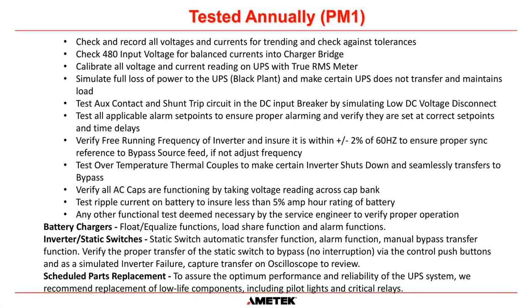We also test the over temperature thermocouples. So there are thermal switches on the heat sinks of all of our semiconductor devices. And if the temperature gets above 90 degrees Celsius, then the inverter will shut down for the inverter heatsink. And for the charger, the charger will shut off also if it gets above 90 degrees Celsius. So we test those circuits to make sure that that actually does happen.